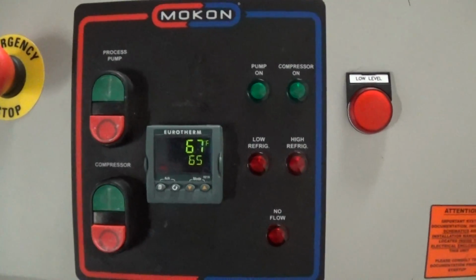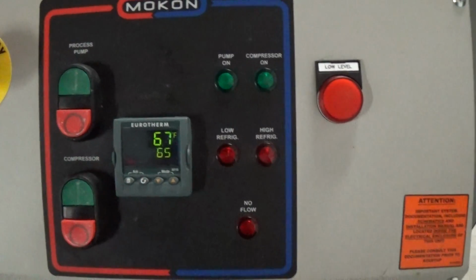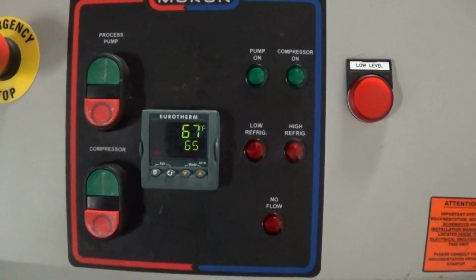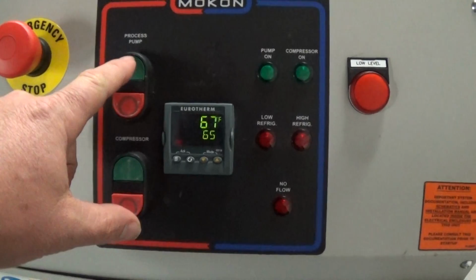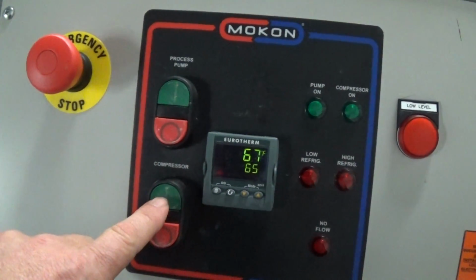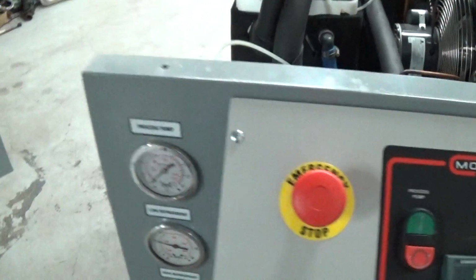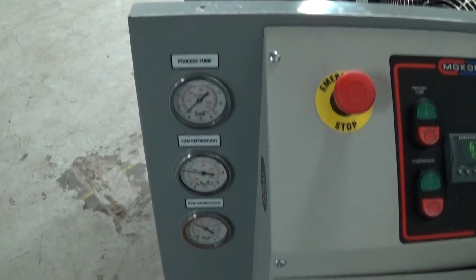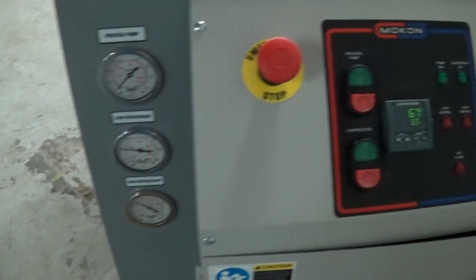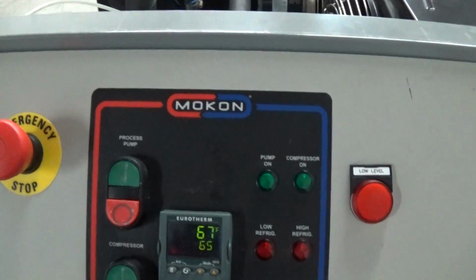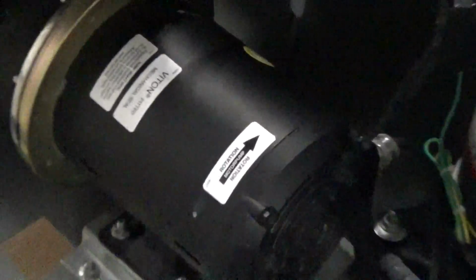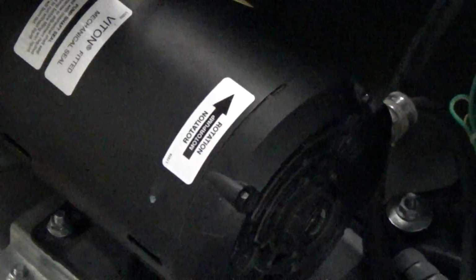So first thing that happens is it's just going to show you the temperatures on the screen here. Now with this controller here, we have a process pump start and a compressor start. We also have nice gauges for both the pump pressure and the refrigerant, high and low refrigerant gauges too. When you first start up, this being a 3-phase machine, it is phase dependent. So you see there on your 3/4 horsepower centrifugal pump, that's the rotation it's supposed to go. You can look down there with a flashlight, check the rotation.